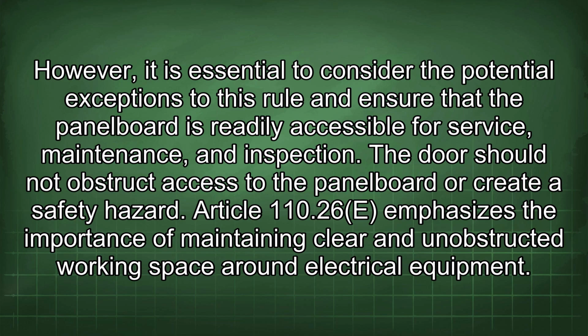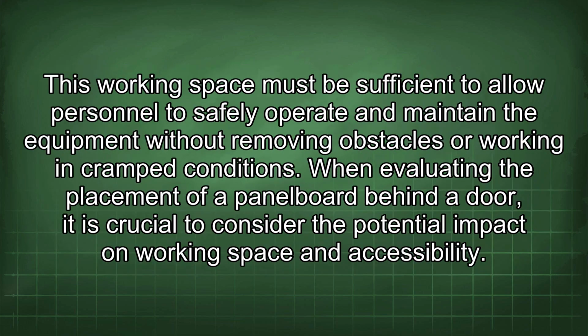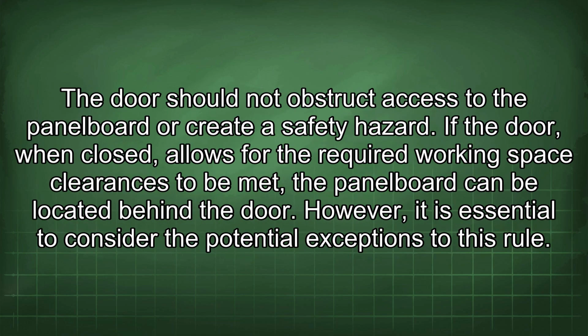Article 110.26e emphasizes the importance of maintaining clear and unobstructed working space around electrical equipment. This working space must be sufficient to allow personnel to safely operate and maintain the equipment without removing obstacles or working in cramped conditions. When evaluating the placement of a panel board behind a door, it is crucial to consider the potential impact on working space and accessibility. The door should not obstruct access to the panel board or create a safety hazard.